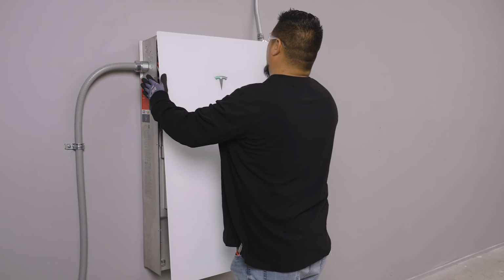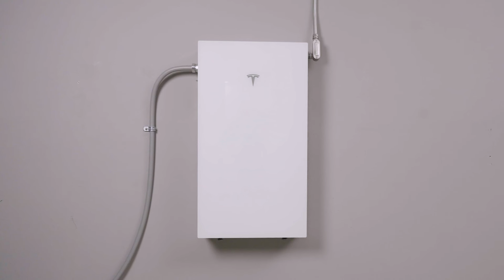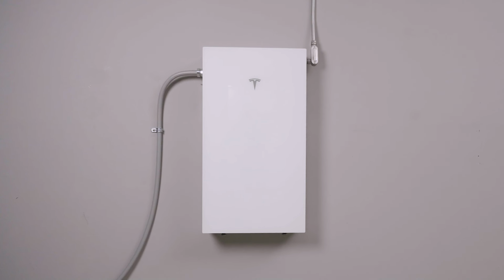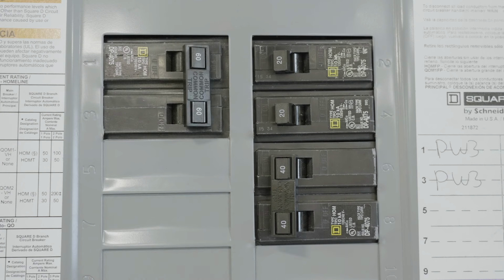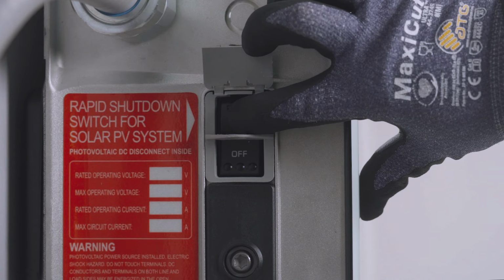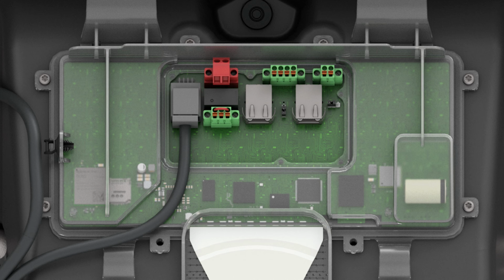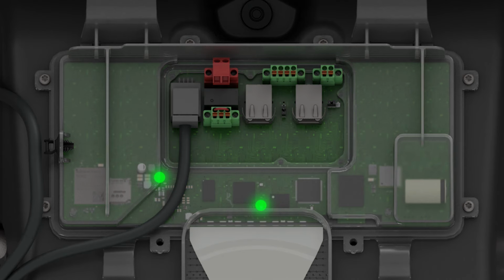With Powerwall 3 mounted and wired, the system is now ready for commissioning. Start by turning the breaker for Powerwall 3 on, then turn on the enable switch. These two LEDs will turn green when Powerwall is turned on. Powerwall 3 is ready to begin commissioning when this LED turns light blue. Note that it may take up to 5 minutes for these LEDs to illuminate.